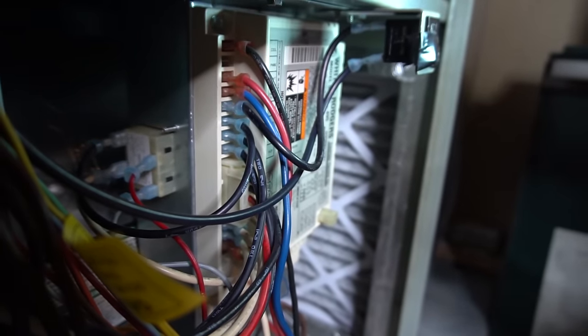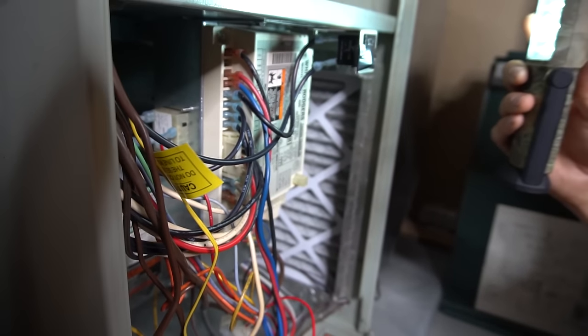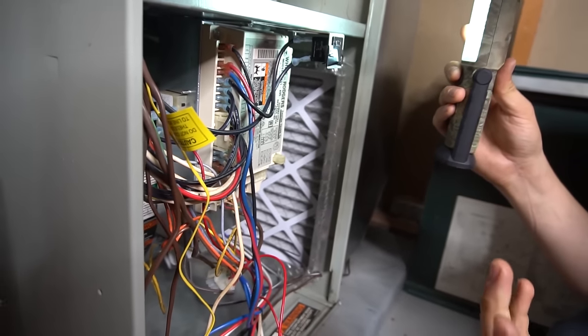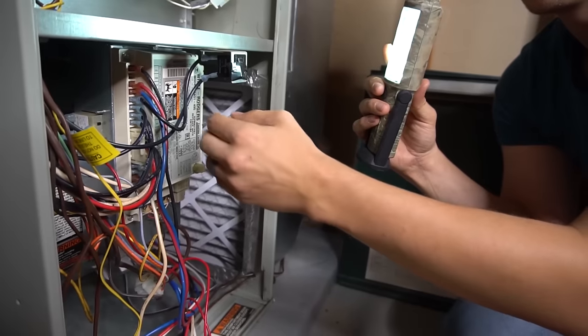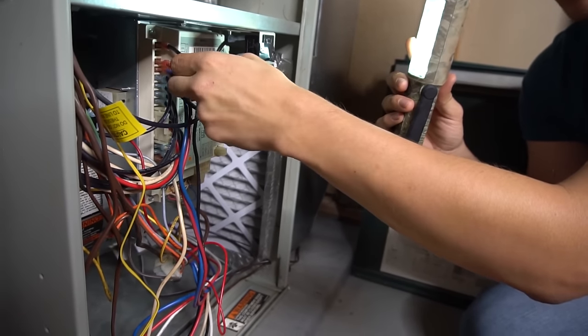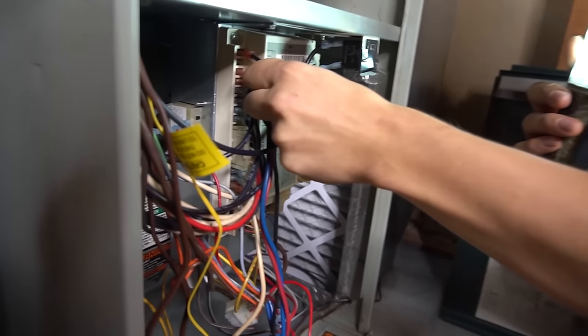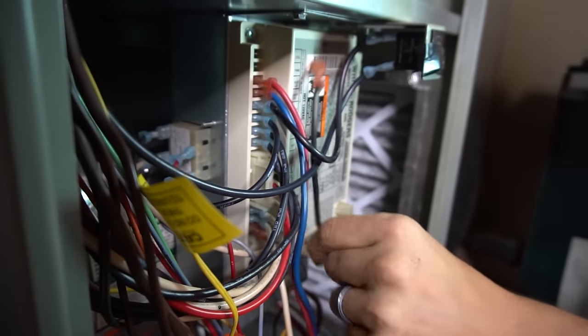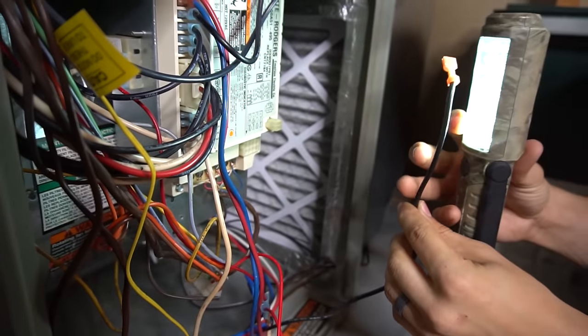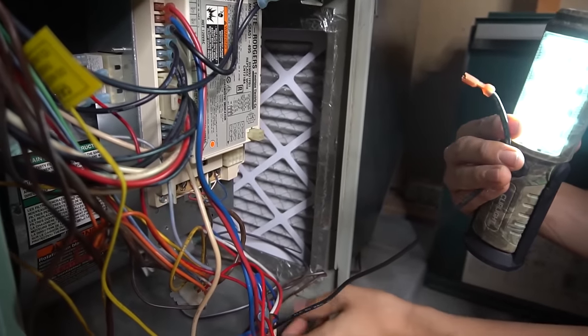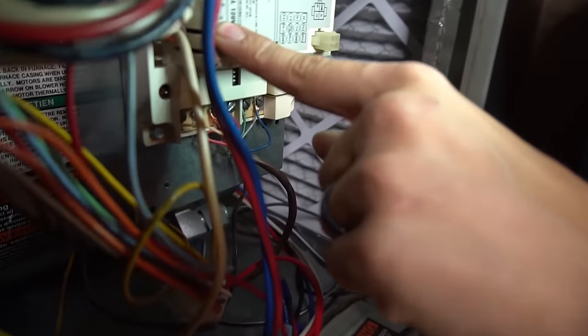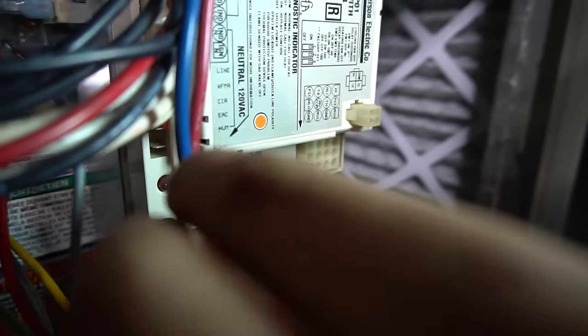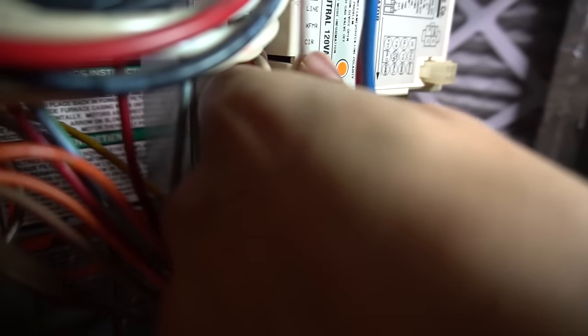So depending on if you're in the furnace season or AC season, right now we're in the AC season, you will pull that wire off. So in my case, it'll be the black wire. I'll pull that wire off like that. And also I will find where my common is coming from the motor. And usually it'll say circ or circulator. And I will pull that off as well.